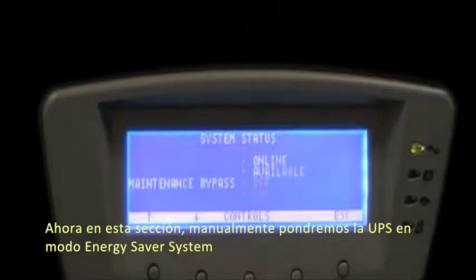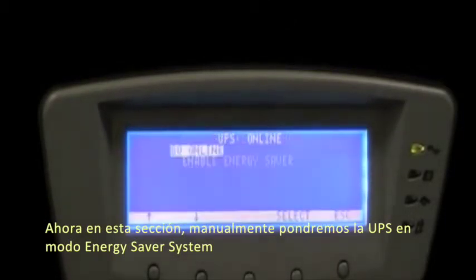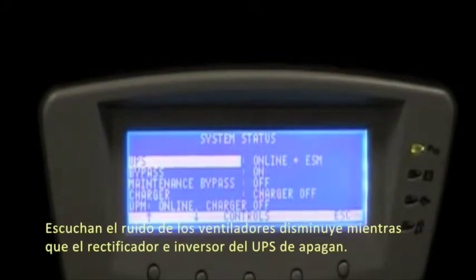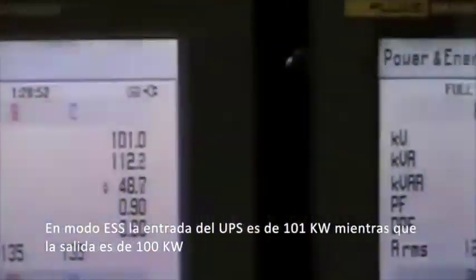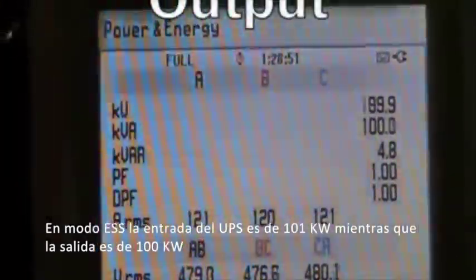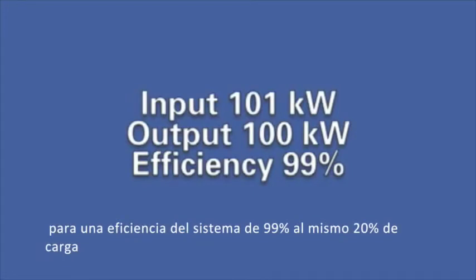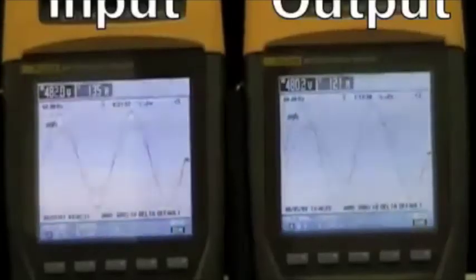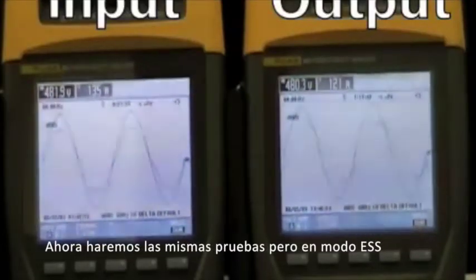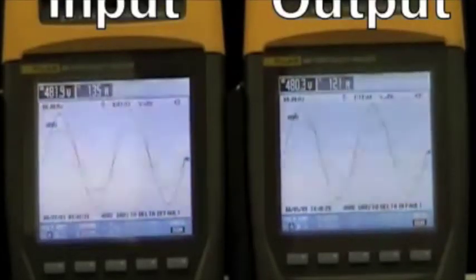Now in this section, we're going to manually place the UPS in energy saver system. You hear the fan noise decrease as the UPS rectifier and inverter shut down. In ESS mode, the input kW is 101, the output kilowatts is 100, for a system efficiency of 99%, again at 20% load. Now we'll perform exactly the same tests that we did before in double conversion mode.